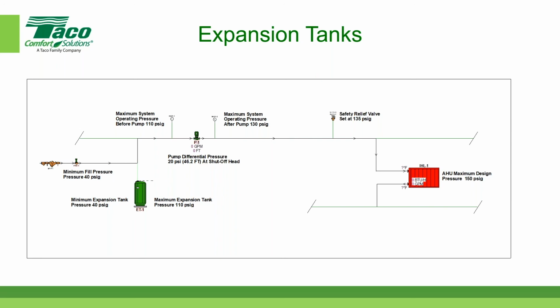Some project gets built, and let's say we happen to be in New England, or let's take the Middle East, for example. So let's say the project gets built and the system gets filled, but the startup of the chillers is not going to take place right away. Well, your temperatures out in the Middle East could be very, very high. So you could have an empty building sitting with water inside the piping system, and the ambient temperature could get up to, say, 100, 110 degrees, in which case, as long as the chiller is not running, the water would expand to that new ambient temperature and eventually would set off the relief valve if you didn't pick a high enough temperature. So for New England, I pick 110 as my maximum temperature in case the building is sitting idle during the hottest part of the year. In other parts of the world where you have very, very high temperatures, you might go to 120 for your maximum temperature or even higher than that. That's the logic behind the chilled water system.